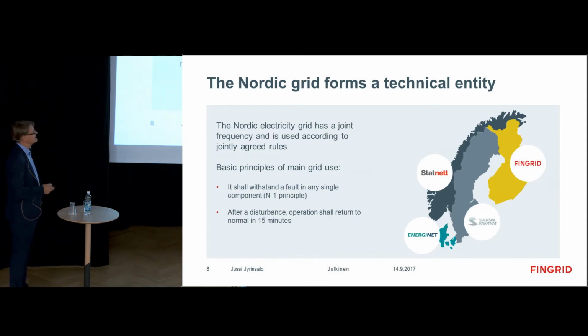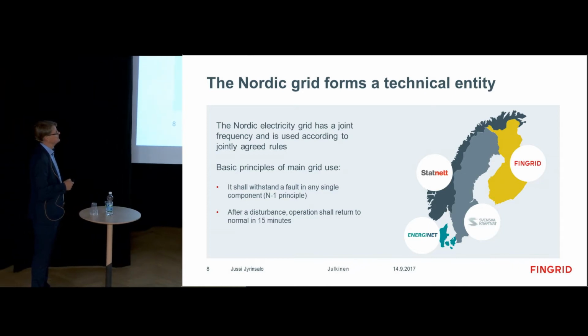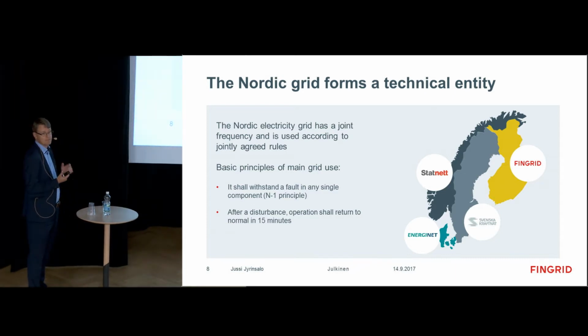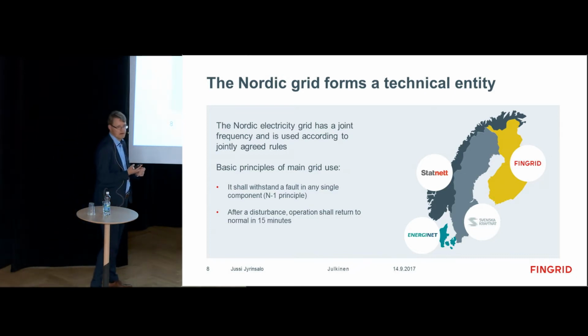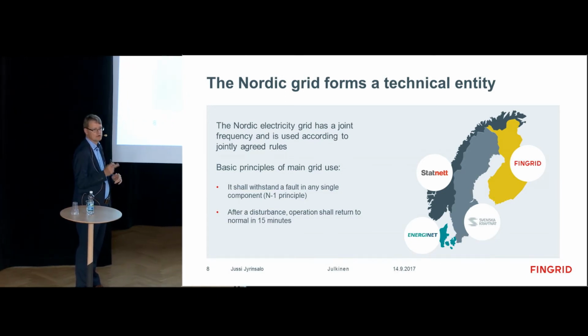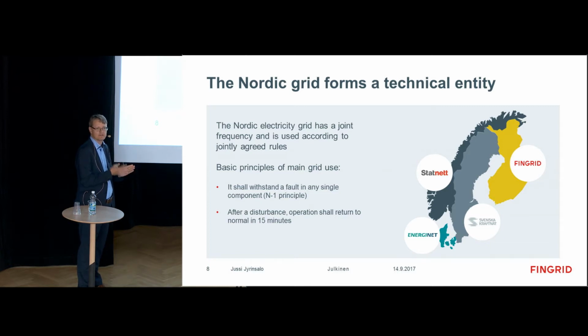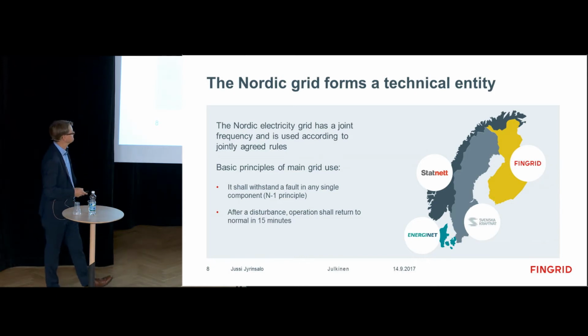All is done in such a way that the system, in any situation, can withstand any fault. So any one of the big power plants, any transmission line, any bus bar in our substation may be faulted and nobody sees it. The system is N-1 tolerable, so you can lose one component at a time, and then in 15 minutes you need to get the system back to a state where it can tolerate another fault. That's the basic principle of how the system is used.